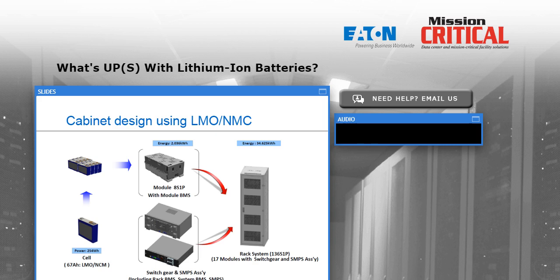On that circuit board, as you can imagine, you have communication and sensing, but you also have power transistors that act to regulate how much charge current this battery receives and make sure the voltages are balanced between those batteries at all times. And if one battery starts acting up thermally or otherwise, the controls have the ability to literally bypass that one battery and leave the rest of them in the circuit. So there's a lot more management, not just monitoring, of the battery system in any lithium-ion battery solution.